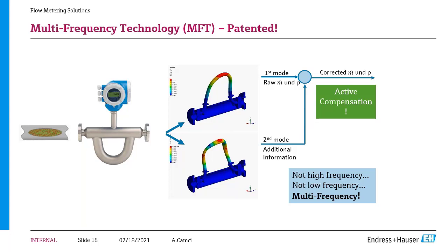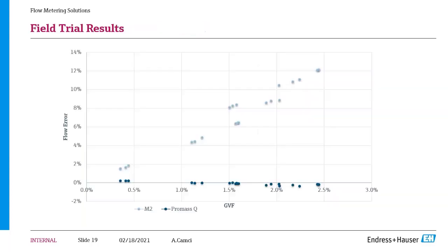how air is moving in these two different frequencies, and we can make active compensation inside the electronics of the meter to reduce the measurement error that happens because of the entrapped air. In the next slide, I will show you some field trial results.